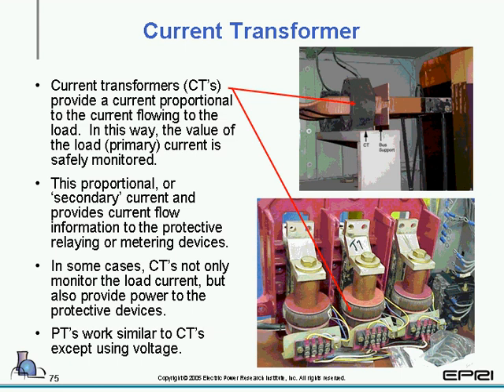are current transformers. Current transformers basically provide a ratio between the primary current and a secondary current in proportional ratio to the primary current. This secondary current is then used to feed protective device metering, and in some cases can be used to actually power up the protective devices. PTs work similar to CTs except using voltage.